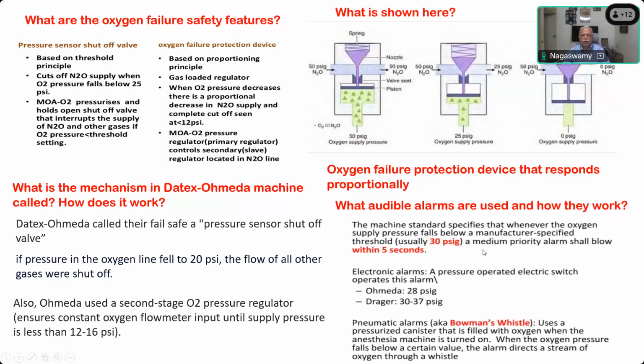So the machine standard specifies that whenever oxygen supply pressure falls below the manufacturer specified level, that is usually 30 psi, a medium priority alarm shall blow within 5 seconds. The electronic alarm, a pressure operated electric switch, operates the alarm. In Ohmeda, it is 28 psi, in Draeger 30 to 37 psi.